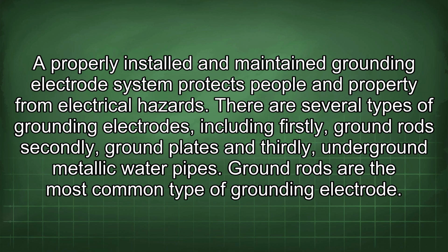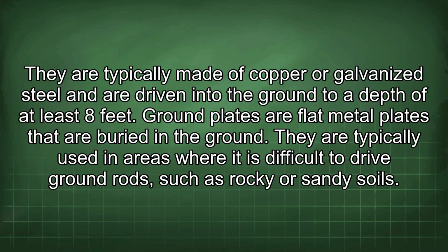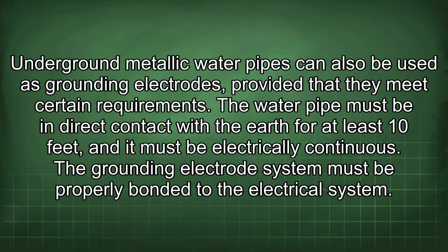There are several types of grounding electrodes, including firstly, ground rods, secondly, ground plates, and thirdly, underground metallic water pipes. Ground rods are the most common type of grounding electrode. They are typically made of copper-clad steel or galvanized steel and are driven into the ground to a depth of at least 8 feet. Ground plates are flat metal plates that are buried in the ground. They are typically used in areas where it is difficult to drive ground rods, such as rocky or sandy soils. Underground metallic water pipes can also be used as grounding electrodes, provided that they meet certain requirements.